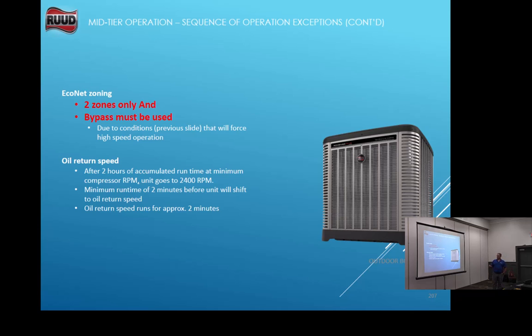Oil return. After 2 hours of accumulative runtime, the compressor goes into an oil return speed of 2,400 RPMs. If it's running on the drive, if it's running on line voltage, it will run up to 3,600 RPMs for 2 minutes to bring back oil to the system.